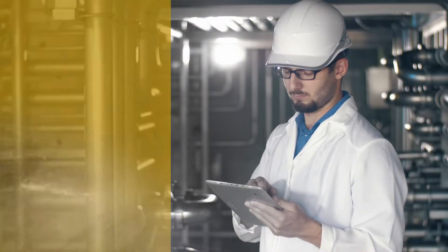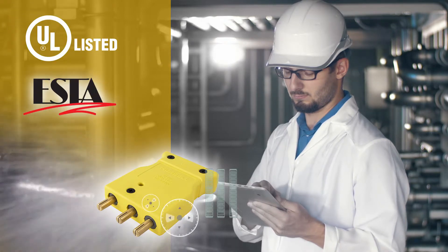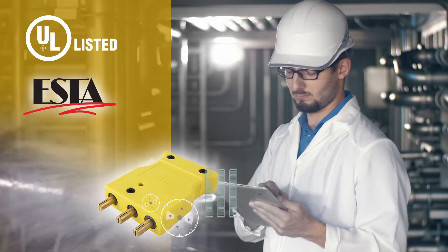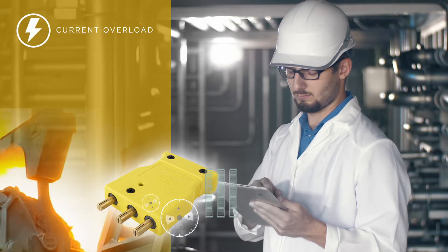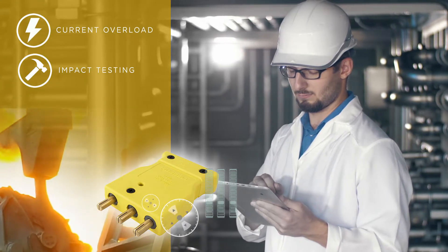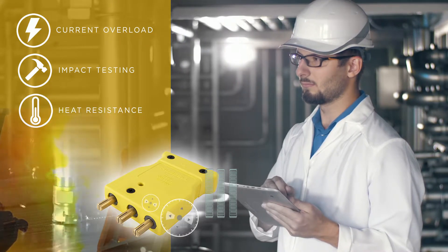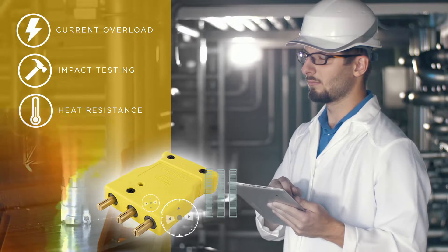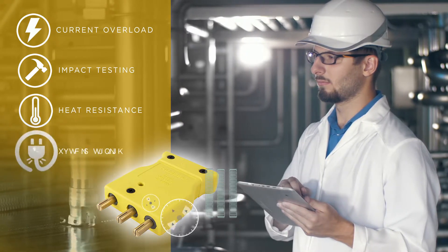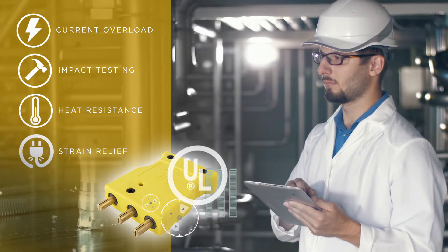Extensively tested for durability, these devices are both UL certified and ESTA compliant. Testing included 150% electrical current overloading of the device, drop impact testing in both regular and sub-zero temperatures, heat resistance testing with devices run for 25 days continuously at fully rated current, and strain relief testing to 60 pounds. This device greatly exceeds UL requirements.